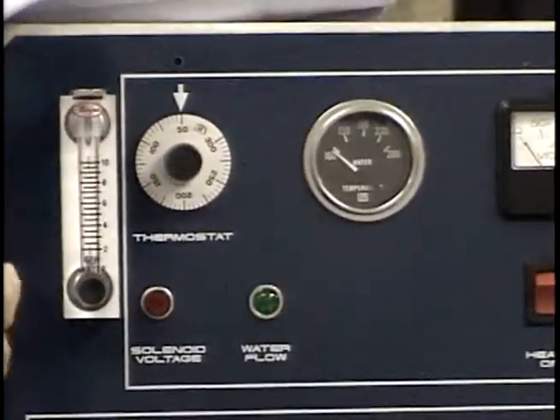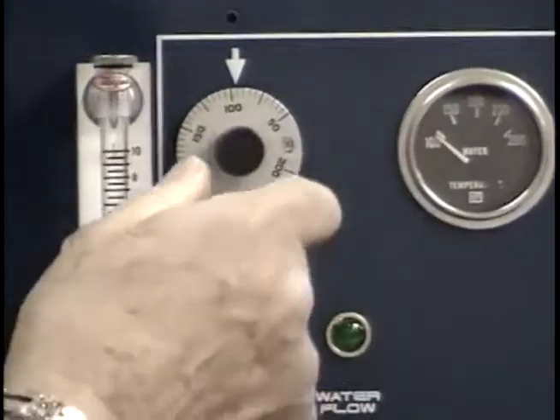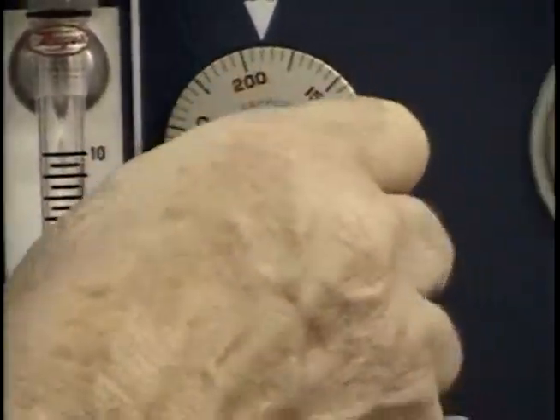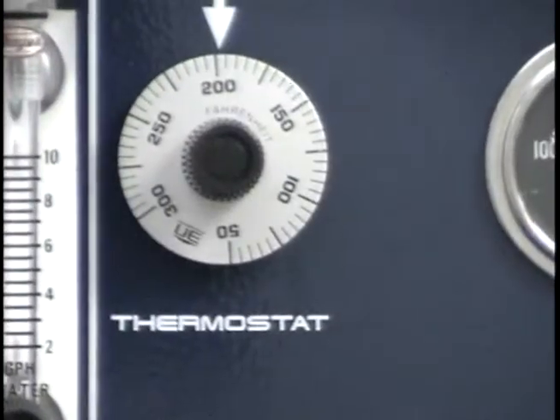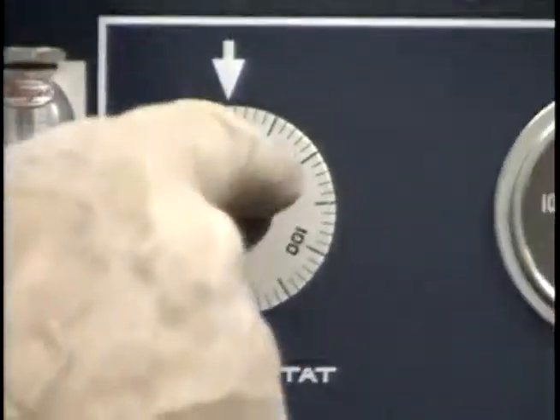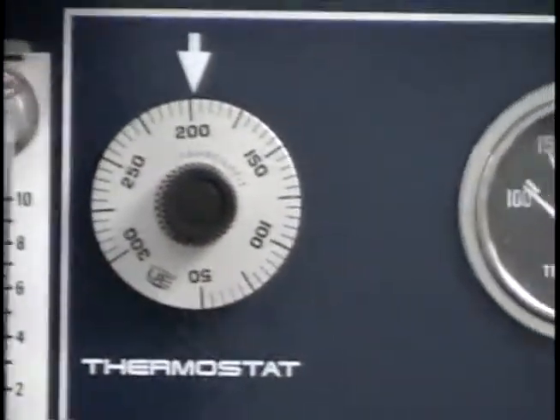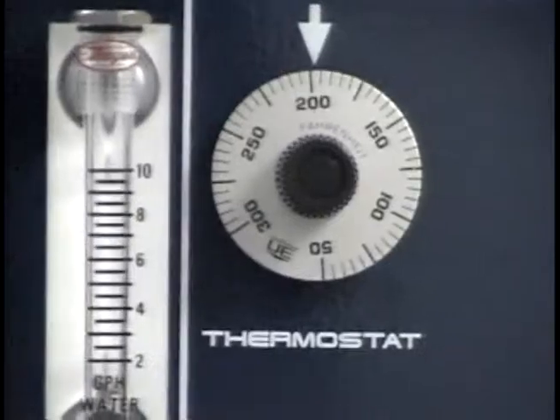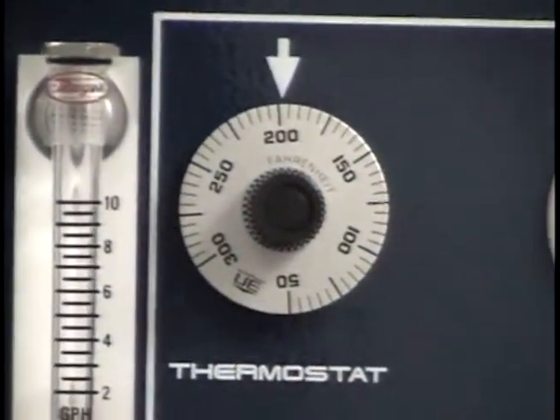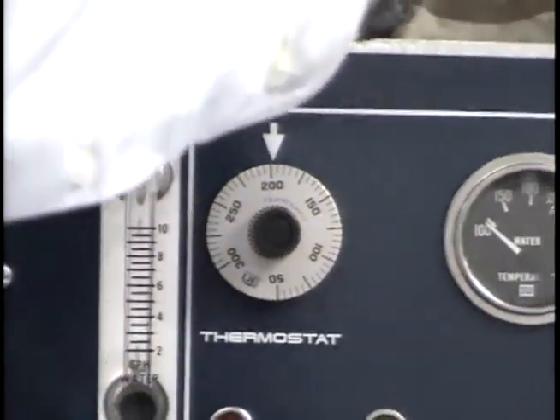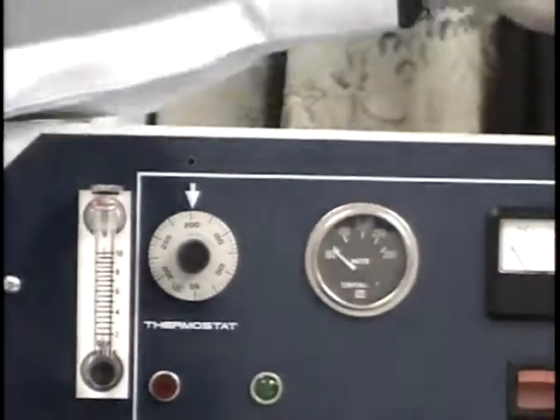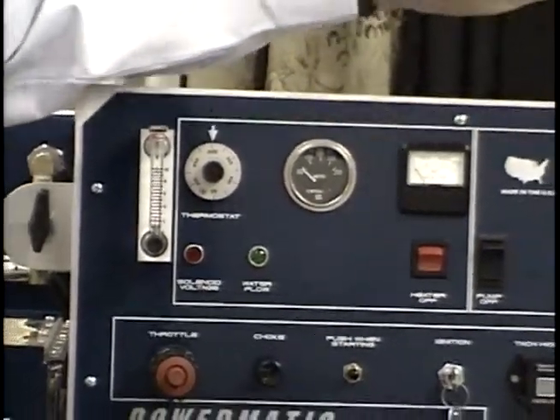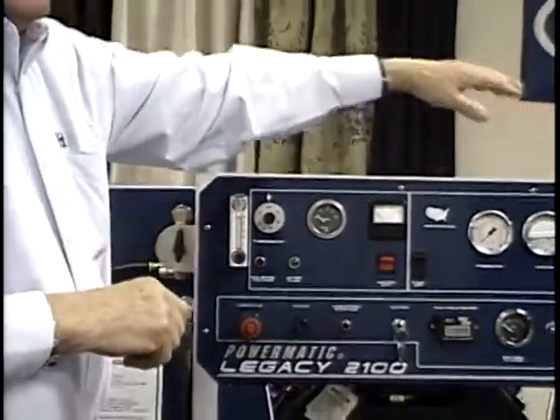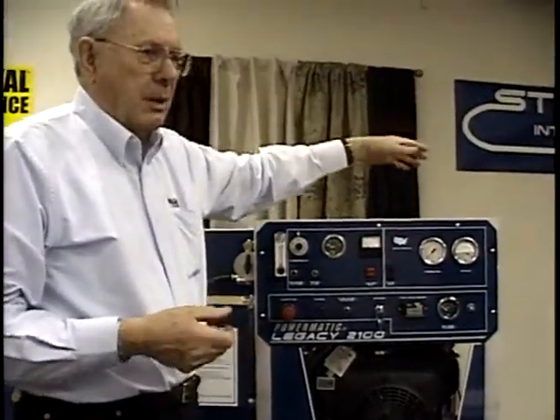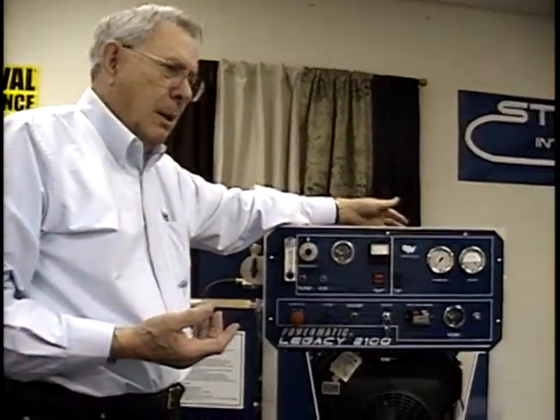It should turn off very near the temperature you set in. If you set 200 degrees, it should turn off at about 200 degrees. Now, one thing about how this system is designed: let's say I set 200 degrees and the heat comes up. When it reaches 200, you should hear it shut off, but it will override a few degrees and then start back down. You'll hear the burner come back on again, then go below and back above the set-off point. That's a natural phenomenon of this machine; it'll work that way. Now, if there's an enormous underride or override, that might tell us there's a problem that needs to be looked at.